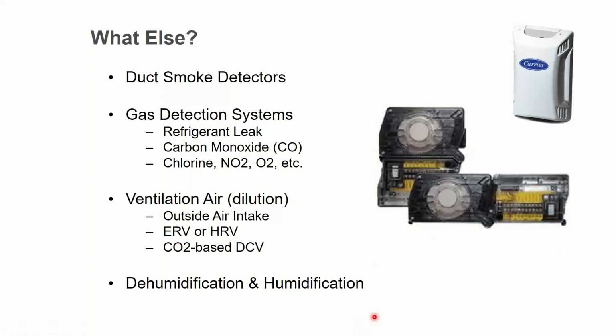Okay, we'll keep on moving here. Other things. If you have spaces that are doing stuff, I mentioned carbon monoxide, right? Boiler rooms, stuff like that. If you've got swimming pools, chlorine sensors, parking garages, NO2 for the diesel vehicles, loading docks. If you have a chiller room, refrigerant leak, there's all kinds of things.